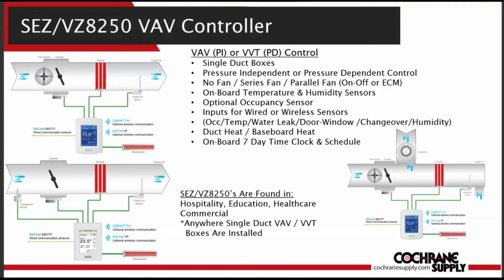They also have the capability to operate series or parallel fans with either an on-off or ECM fan motor. On board, the controllers have temperature and humidity sensors. There's an option for an onboard occupancy sensor as well. The controller itself has 7 inputs in addition to the onboard sensors for hardwired sensors like supply temperature or changeover sensor or remote space temperature sensor, as well as the option for communicating to battery-powered wireless sensors for temperature, humidity, CO2, occupancy, door and window switches. If you're using these controllers for VAV box control, it has an input for a pressure transducer of your choice to connect to the VAV box flow ring.